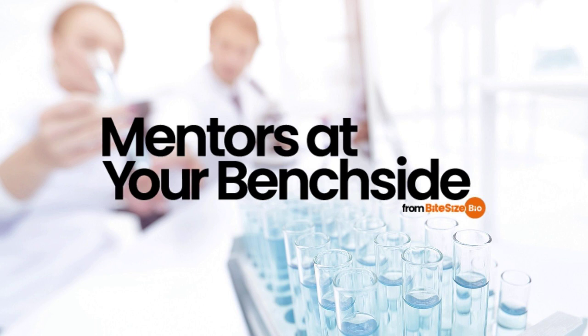You can refill the pH meter probe with saturated potassium chloride, but be sure to confirm that the pH meter still works by measuring the pH of several reference solutions that you know the pH of. To prevent the solution inside the probe from leaking and/or evaporating, the probe should be stored in a solution of 3 molar potassium chloride. It should not be stored in H2O, and especially not distilled H2O, because we need the conductive potassium chloride solution. Dialyzing it all away is not good.